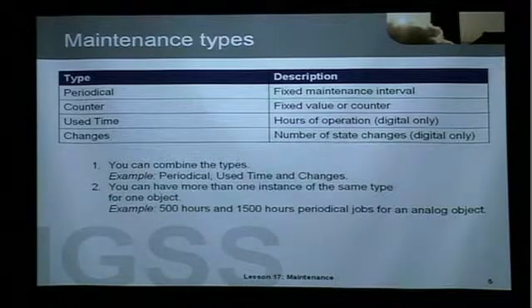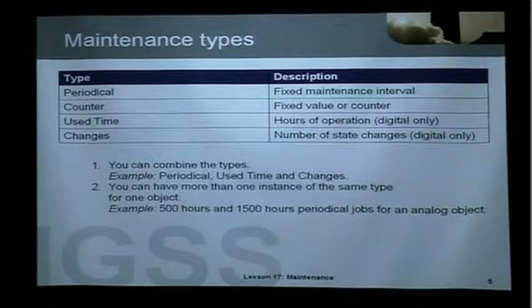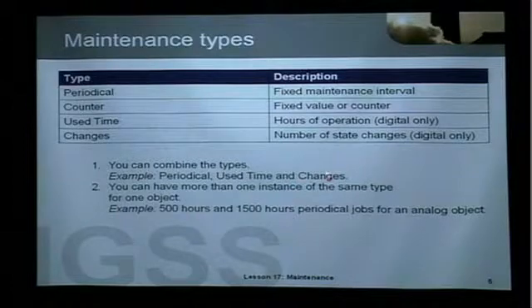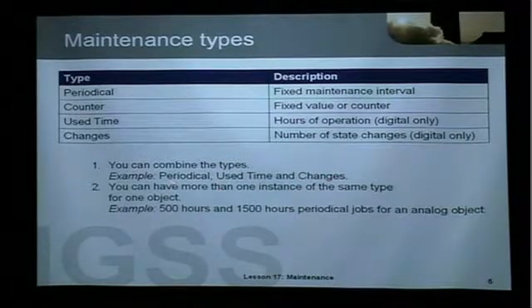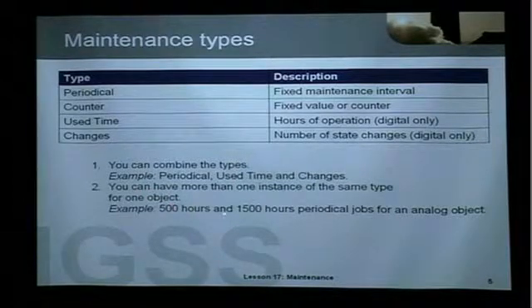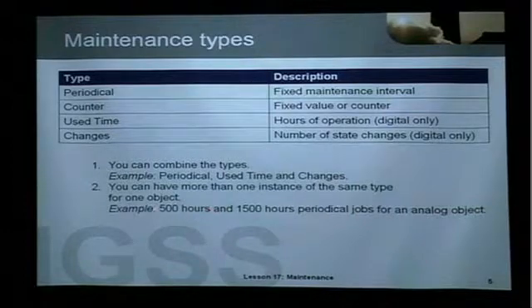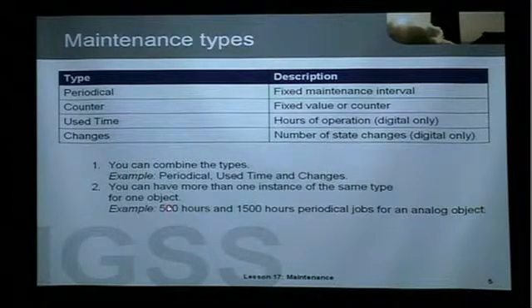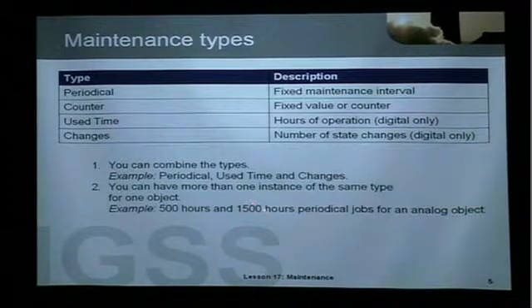Two things to notice: you can combine these types. So you could have both periodical, use time, and changes for a digital object. You can also have more than one instance of the same type for one object — for example, two periodical jobs saying that after 500 hours you do maintenance task 1, and after 1500 hours you must do maintenance task 2.